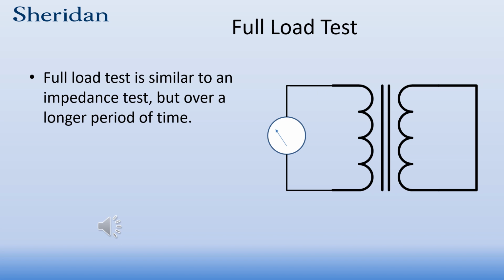Next, what we're going to do is a full load test. A full load test is similar to the impedance test. However, what we're doing here is we're going to make the same connections. We short out the secondary. We apply a variable voltage supply to the primary. However, this is done over a longer period of time.